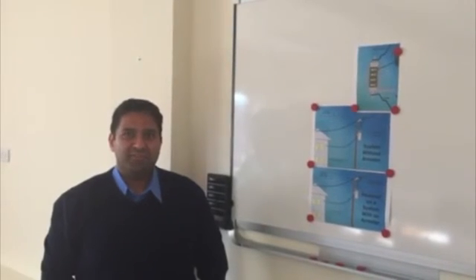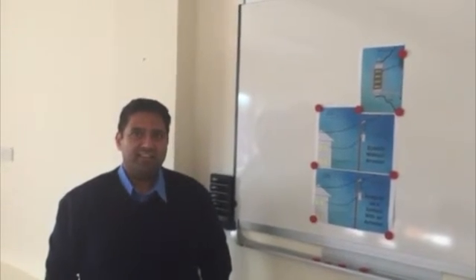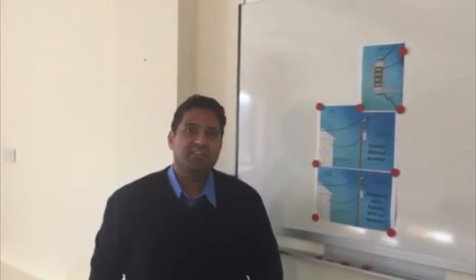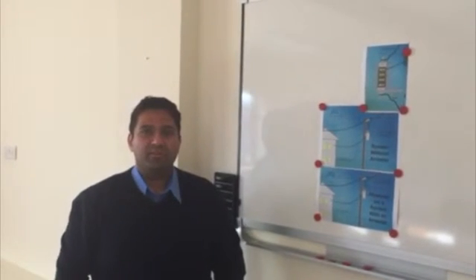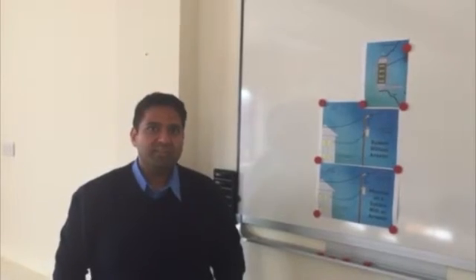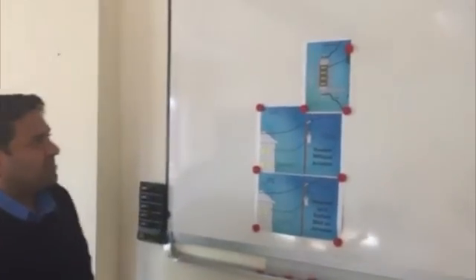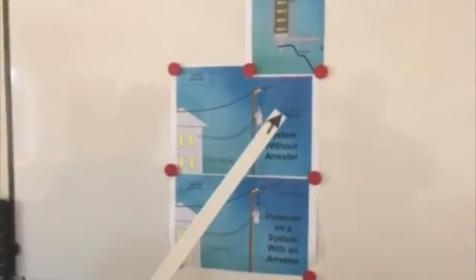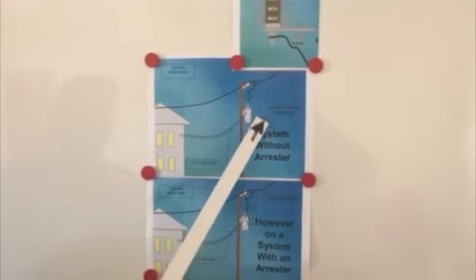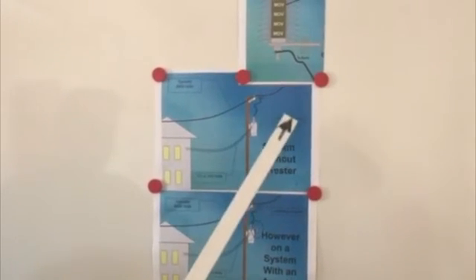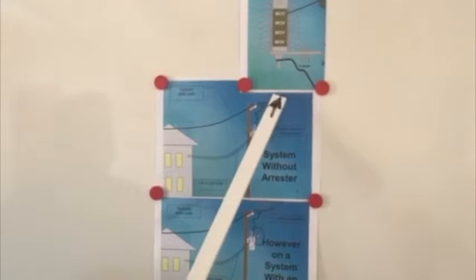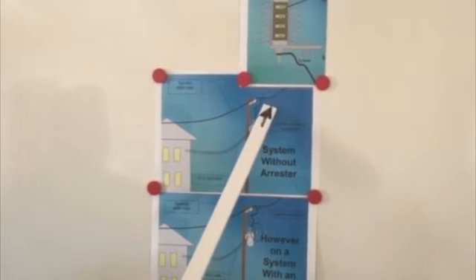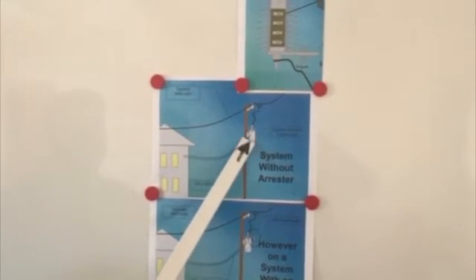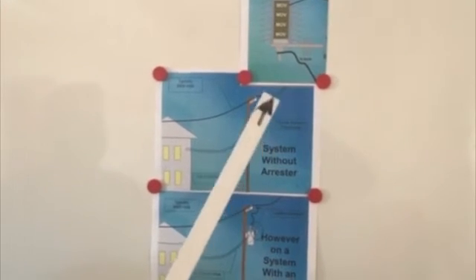One method of surge control is via a surge arrestor. These work by diverting a lightning strike to the ground rather than passing it to sensitive equipment. You can see here a system without a surge arrestor fitted, where the cable joins onto the transformer feeding the house. If there was a lightning strike, it would hit the main line and the large voltage would travel through the transformer, possibly causing a failure.